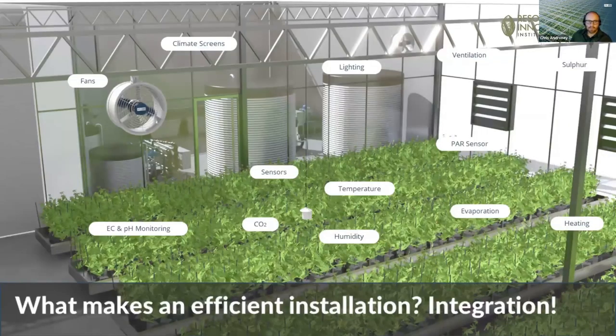Next slide. So here's a good example of just a small portion of a greenhouse installation. On this illustration, we can see lots of equipment: fans, climate screens, lighting, ventilation, sulfur pots, and also quite a few sensors, such as EC and pH sensors, temperature, CO2, humidity sensors, PAR sensors, all kinds of things installed in a greenhouse section. Again, this is just a small portion of what it takes for a successful greenhouse. You may not have all of this equipment, but these are some of the common things involved. All of these pieces of equipment need to talk to each other to make sure that everything's running efficiently and properly. Next slide.